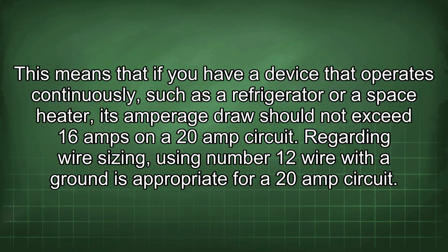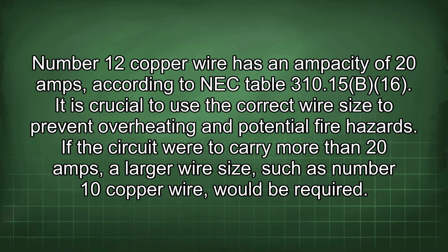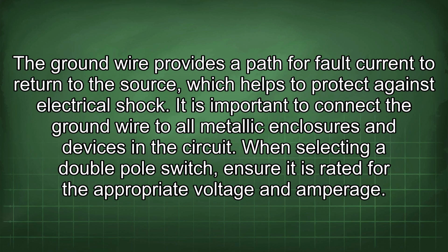This means that if you have a device that operates continuously, such as a refrigerator or a space heater, its amperage draw should not exceed 16 amps on a 20 amp circuit. Regarding wire sizing, using number 12 wire with a ground is appropriate for a 20 amp circuit. Number 12 copper wire has an ampacity of 20 amps according to NEC table 310.15(B)(16). It is crucial to use the correct wire size to prevent overheating and potential fire hazards. If the circuit were to carry more than 20 amps, a larger wire size, such as number 10 copper wire, would be required. The ground wire provides a path for fault current to return to the source, which helps to protect against electrical shock.